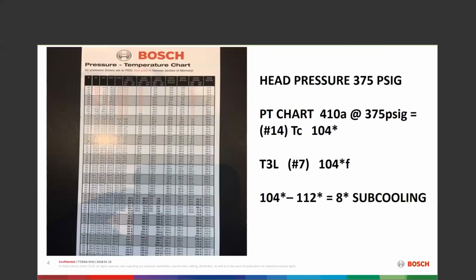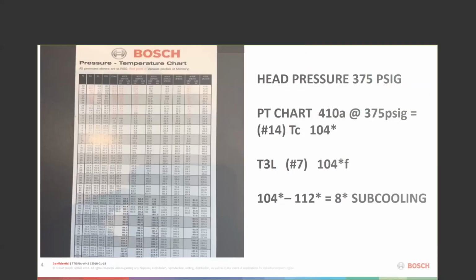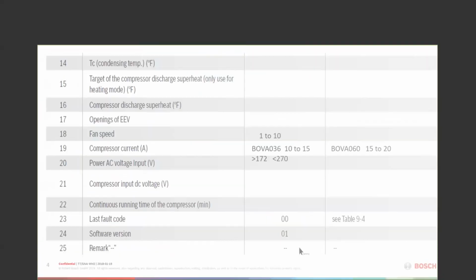Again, head pressure. This particular unit, we're looking at a 375. We're looking at the PT chart at 375. Number 14 was 104. T3L is number 7. That's 104. Redo that. 104 and 112 is looking at 8 degrees of subcooling. So my math may be wrong on this particular chart. I just now saw that. But that is what the chart is for. That is what allows you to take your subcooling readings from the actual unit to the PT chart and put it down so that you can see what this particular machine is doing. There are your numbers.